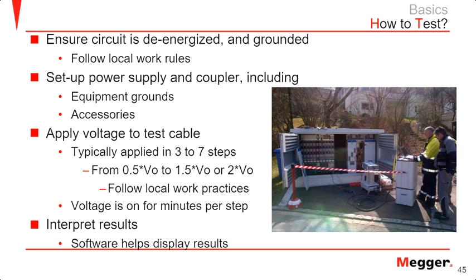Sometimes people start from all the way up, that is 2 times U naught or 1.7 times U naught, and then gradually come downwards, that is 1.5, 1.3, 1.0, 0.7, and 0.5.